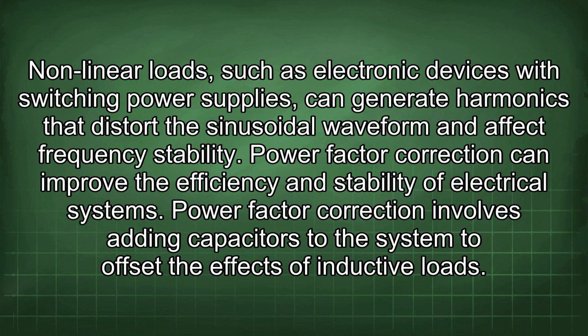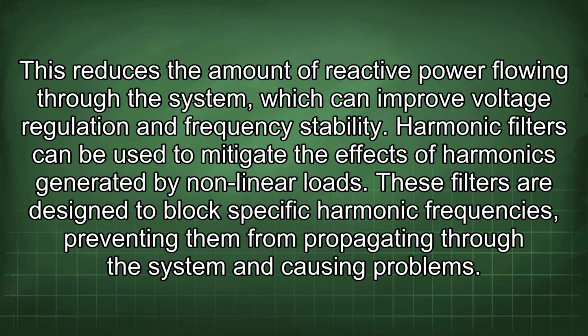and affect frequency stability. Power factor correction can improve the efficiency and stability of electrical systems. Power factor correction involves adding capacitors to the system to offset the effects of inductive loads. This reduces the amount of reactive power flowing through the system, which can improve voltage regulation and frequency stability.